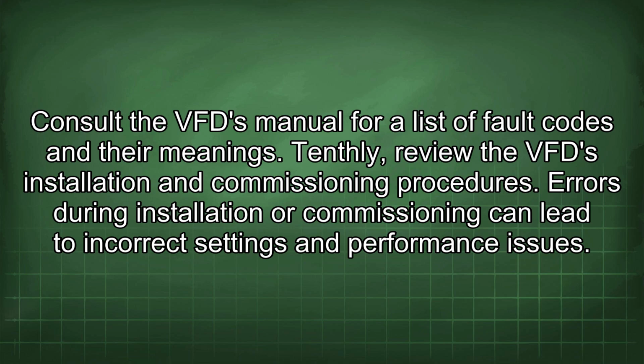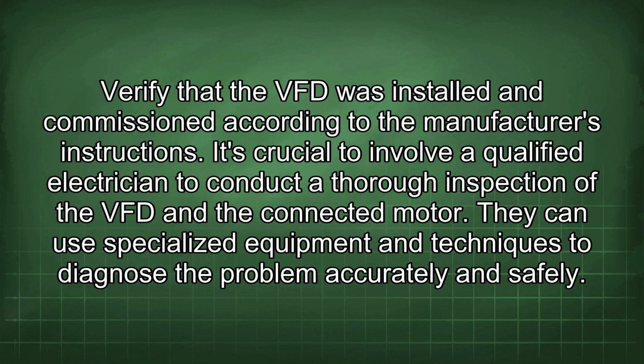Tenthly, review the VFD installation and commissioning procedures. Errors during installation or commissioning can lead to incorrect settings and performance issues. Verify that the VFD was installed and commissioned according to the manufacturer's instructions. It's crucial to involve a qualified electrician to conduct a thorough inspection of the VFD and the connected motor. They can use specialized equipment and techniques to diagnose the problem accurately and safely.